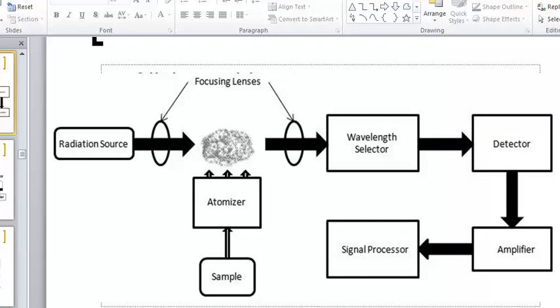which is what we're calling the photomultiplier tube. The photomultiplier tube amplifies the signal, and that amplification is sent to the software, and that software and computer processes that information and gives you a signal that you're seeing on the computer screen. So those are the pieces and parts that are major for the AA instrument.